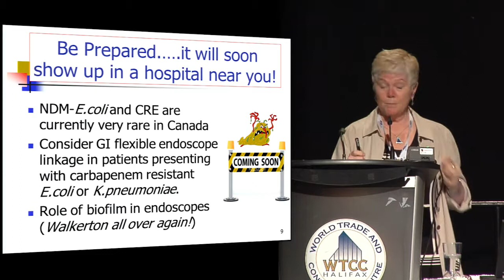So be prepared. Okay, Susie talked about the arthroscopic shavers, and that's great because I can spend less time going over things. But what I wanted to focus on was the fact that in this report, they did a thorough investigative process as well. And although there was residual tissue that was actually shown within the channels of both the trocar that's used for introduction of the handpiece and the handpiece itself, the authors felt that there must have been some type of biofilm buildup. So a piece of tissue that stays inside a cannula, probably when it goes through steam sterilization, is going to probably be totally eradicated of viable organisms the first time it goes through. But as it is undergoing steam sterilization, it's essentially going to stick that piece of tissue onto the stainless steel inner channel, and that tissue obviously is then going to become part of the inner channel as reprocessing is done.